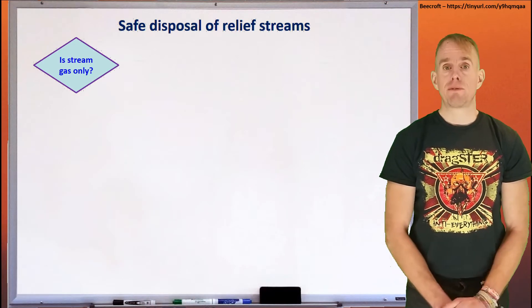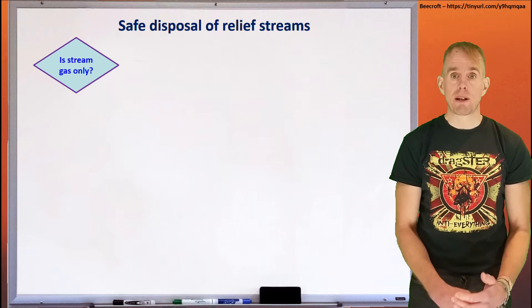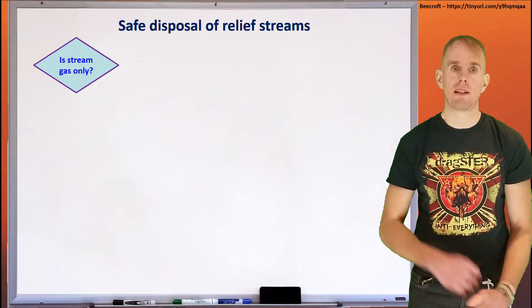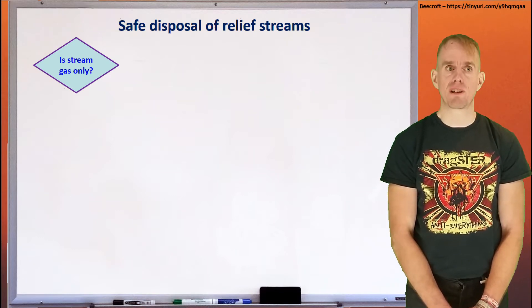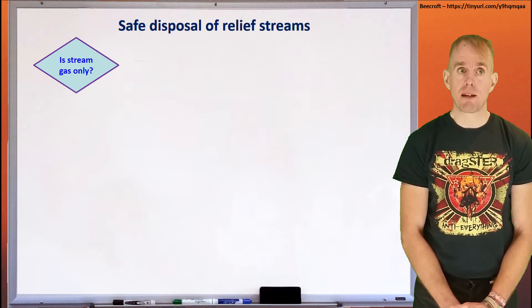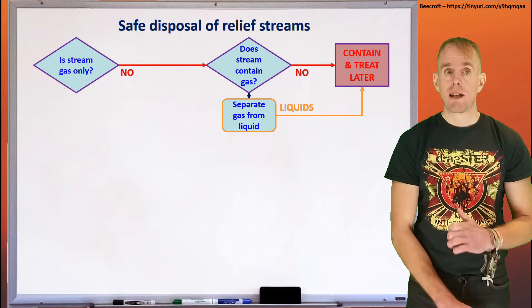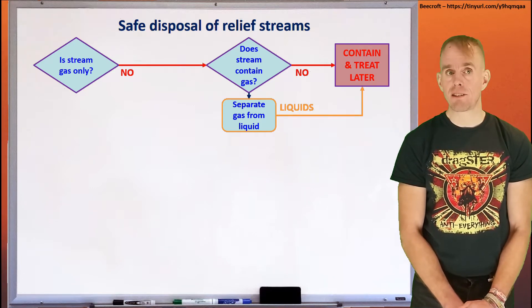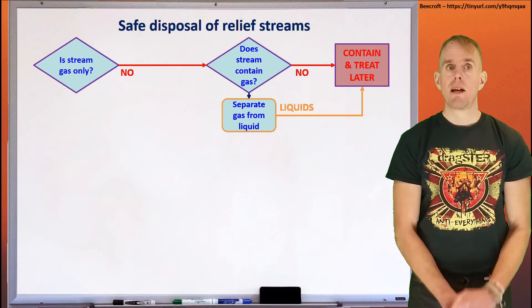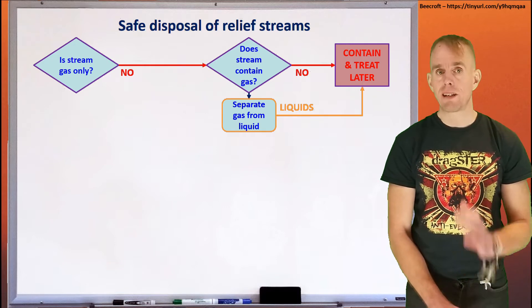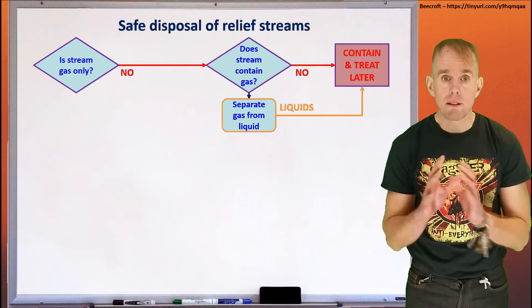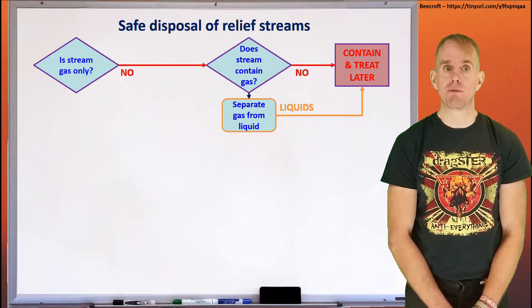In the case of a relief event occurring, you need to do something with whatever is released by that relief event. There's a flowchart here that is very useful to guide you through this process. The first question you have to ask is: is the stream gas only? If not, and the stream contains liquid, then ask yourself does the stream contain gas? If it does, you've got to separate that gas out of the liquid. But if it doesn't contain gas, then for liquid, contain them and treat them later — there'll be some sort of containment where that is a problem for after the relief event is finished.